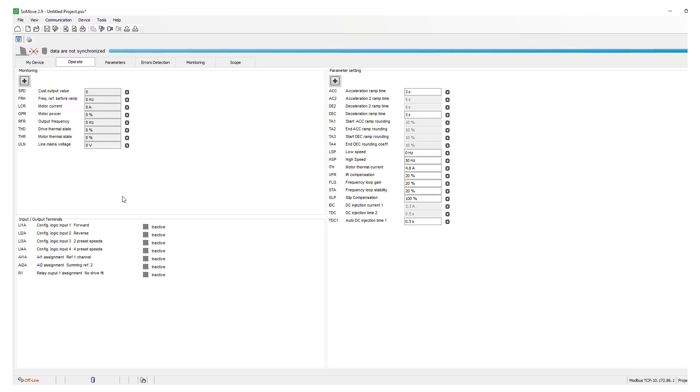Make sure that the motor rotation is correct. If the rotation is wrong then go ahead and correct the rotation by switching any of the two leads on the output of the VFD.